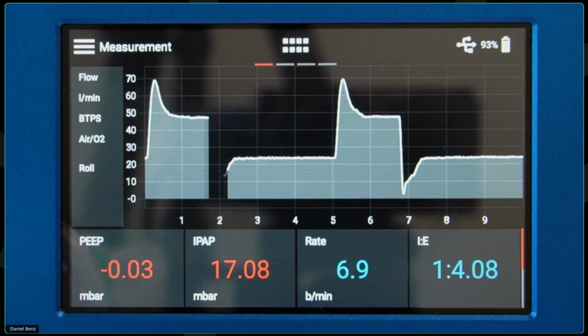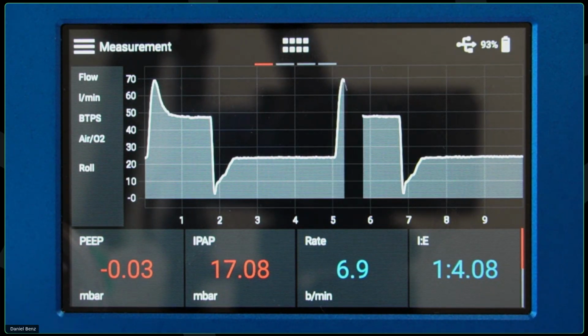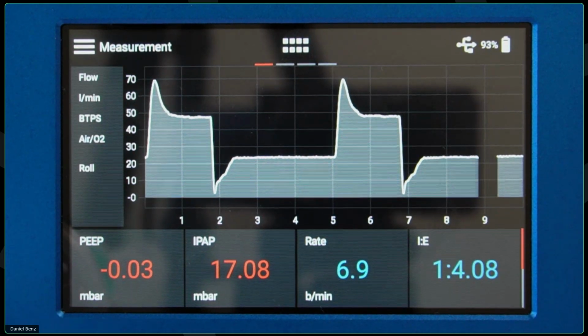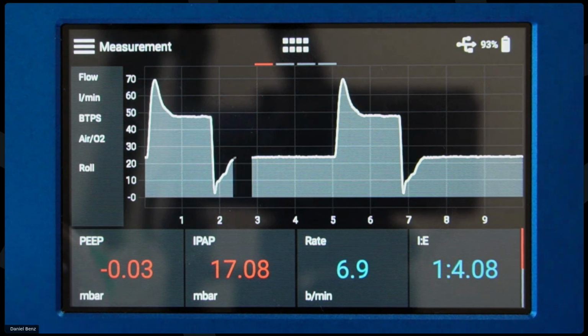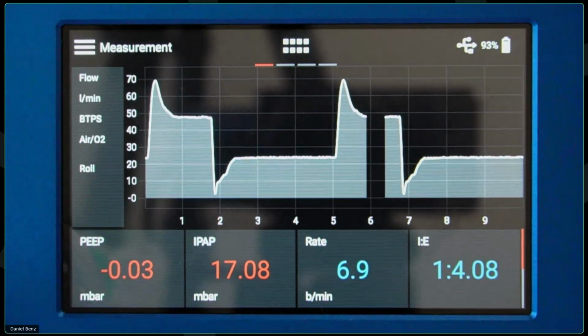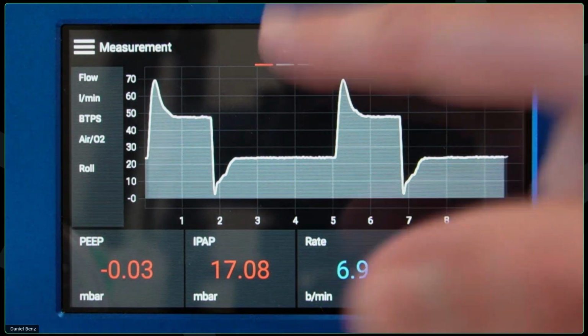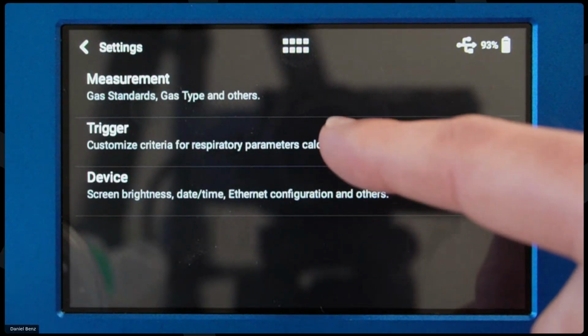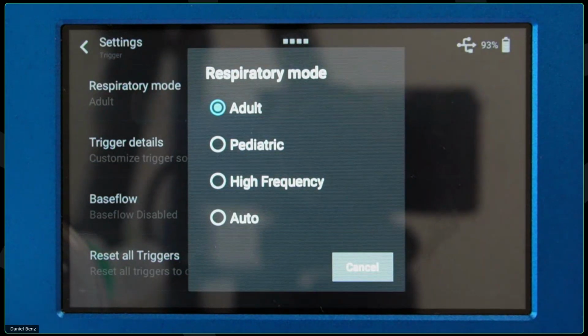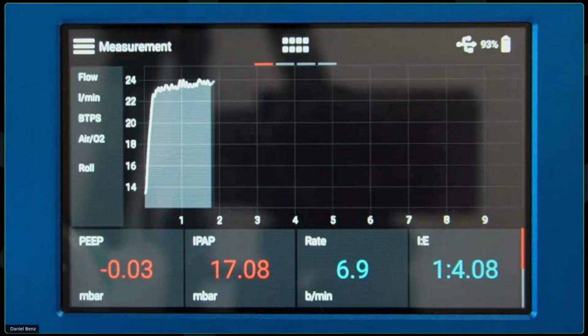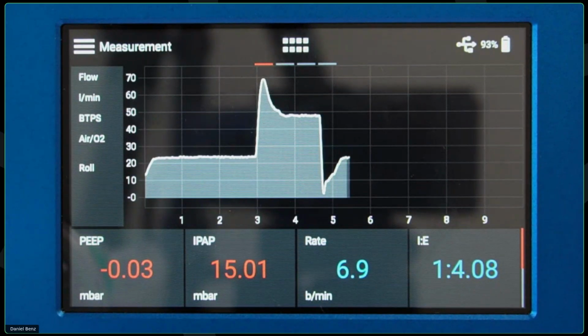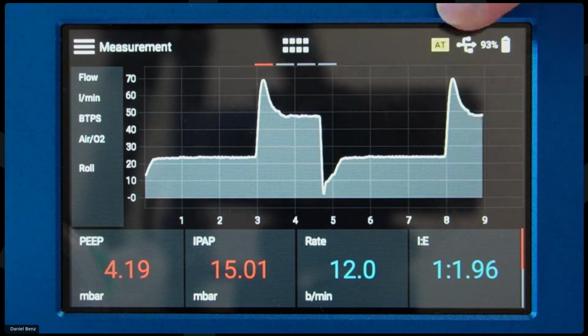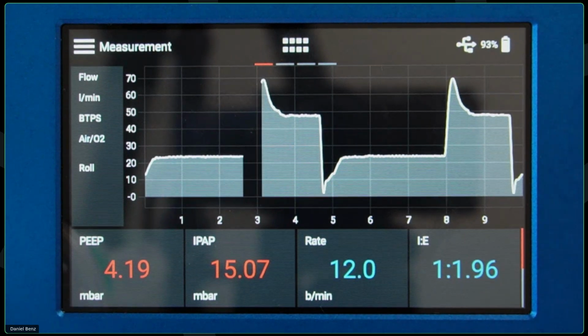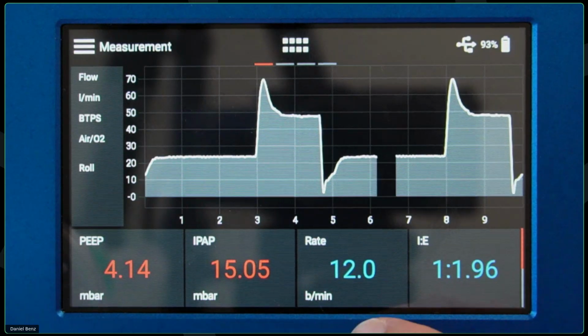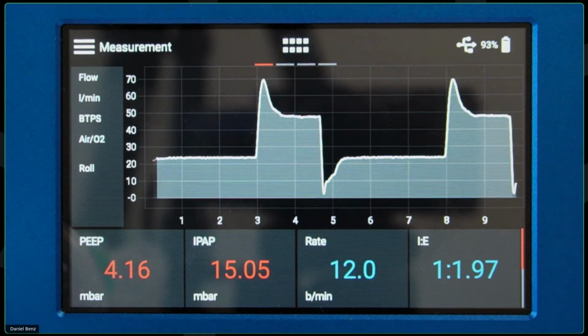So with all other gas flow analyzers on the market, we would now have to analyze the pressure and flow waveforms and see what suitable trigger settings for this application we can find. The FlowAnalyser PRO, however, can do that automatically for us. So when I go into my settings here and choose trigger settings, I can change my respiratory mode to automatic. And what that does is, after a little while, in my measurement screen, I will see it analyzed the flow and pressure waveform already. And now you can see it's triggering again. It's saying AT, that means automatic trigger. And you can see my measurements are actually back, and I can accurately measure my parameters here.